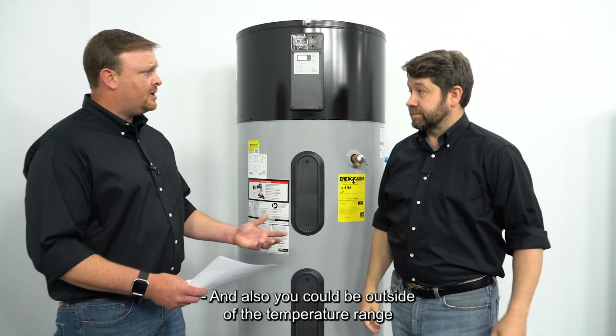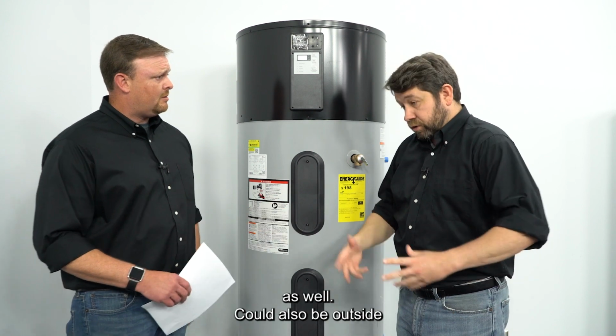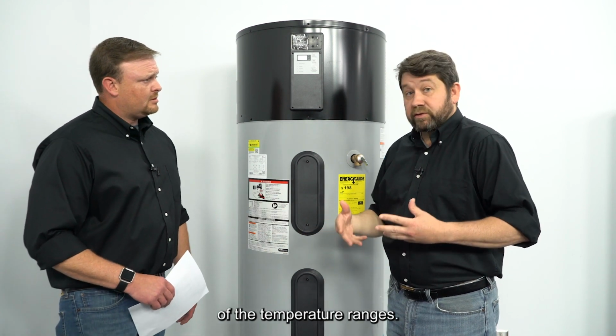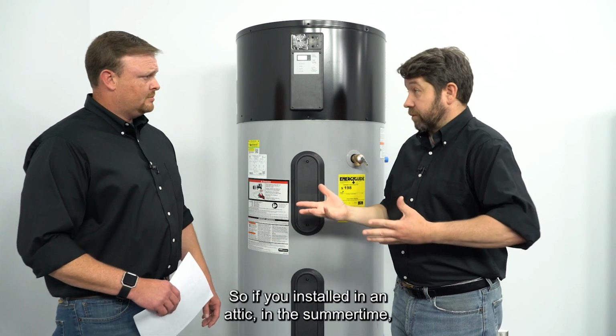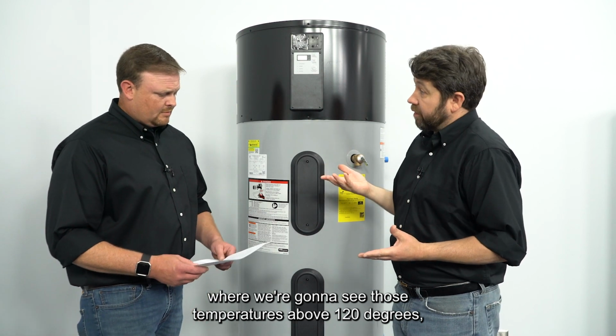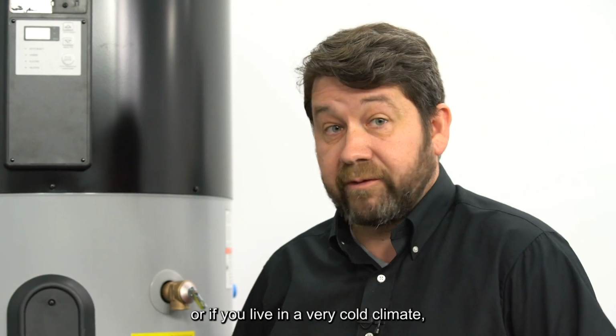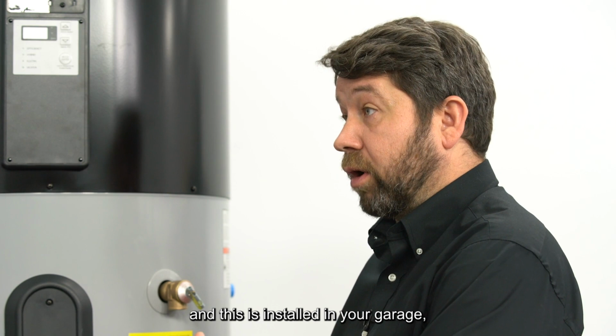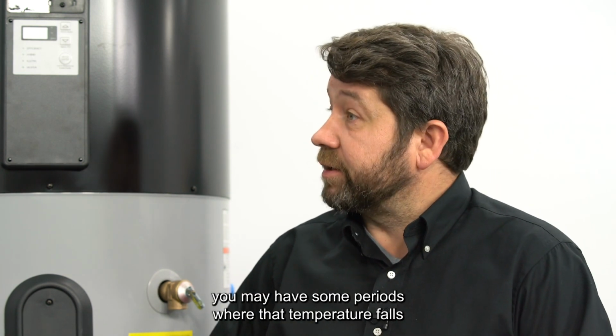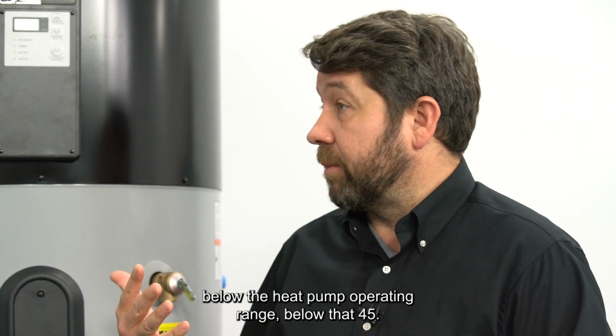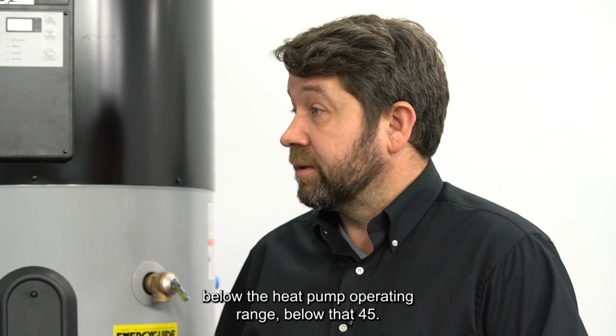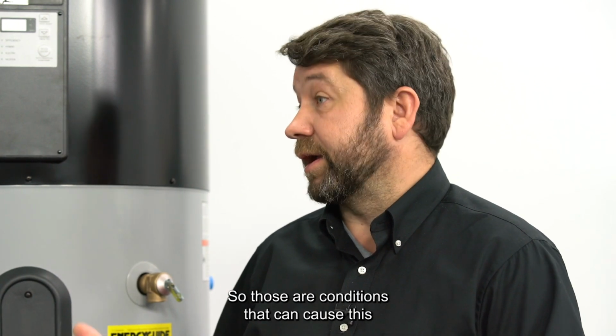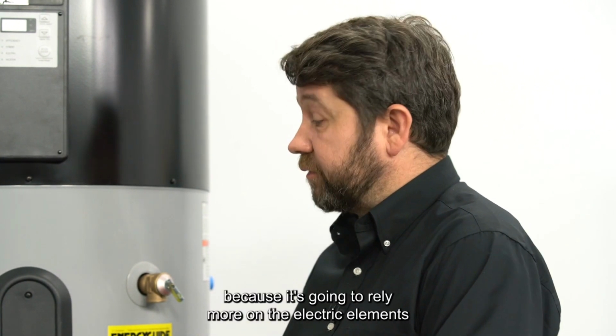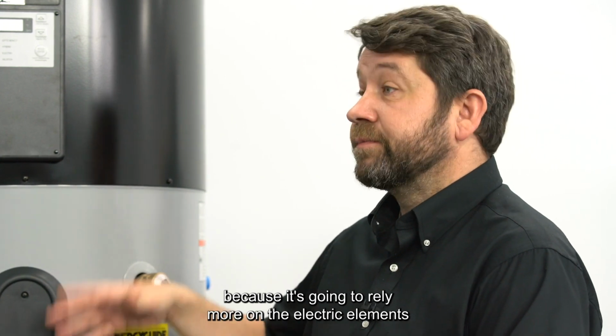And also, you could be outside of the temperature ranges as well. Could also be outside of the temperature ranges, so if you're installed in an attic in the summertime where we're going to see those temperatures above 120 degrees, or if you live in a very cold climate and this is installed in your garage, you may have some periods where that temperature falls below the heat pump operating range, below that 45. So those are conditions that can cause this to not operate as efficiently, because it's going to rely more on the electric elements and less on the heat pump.